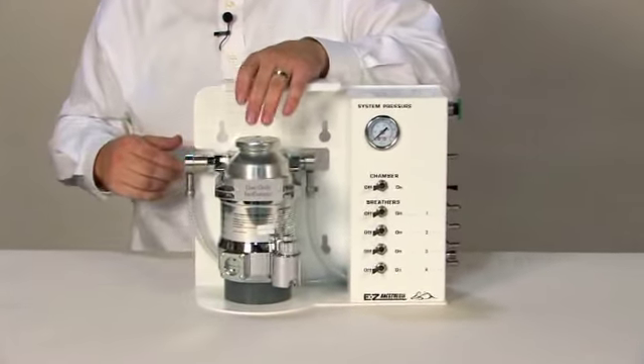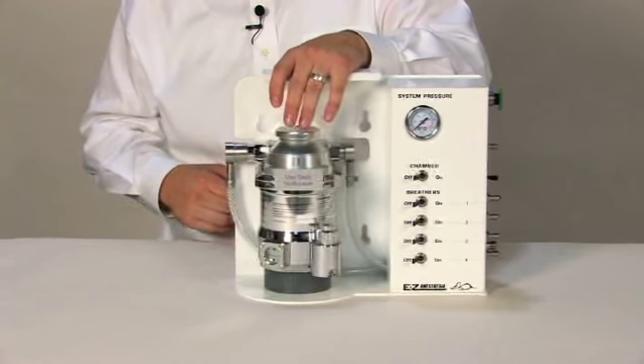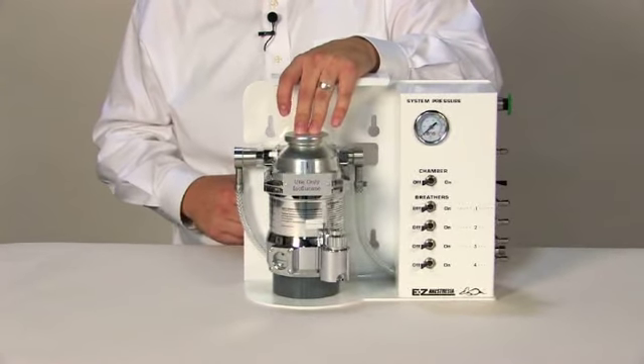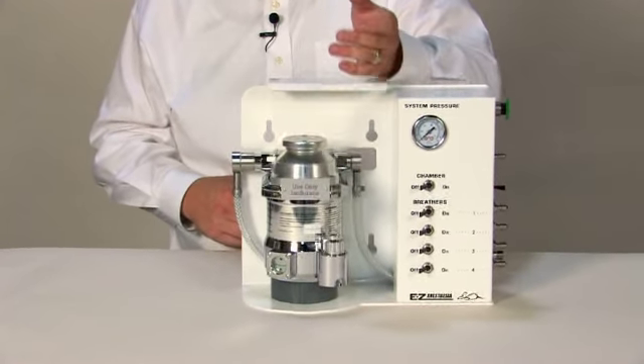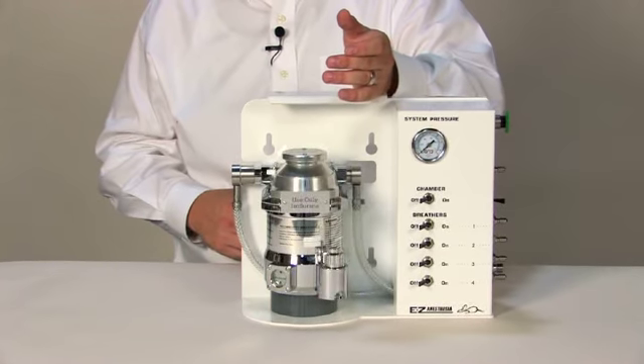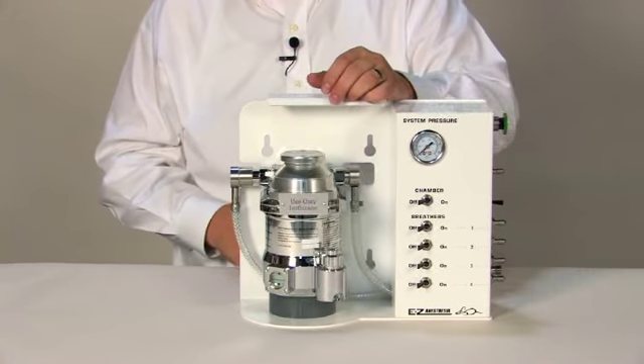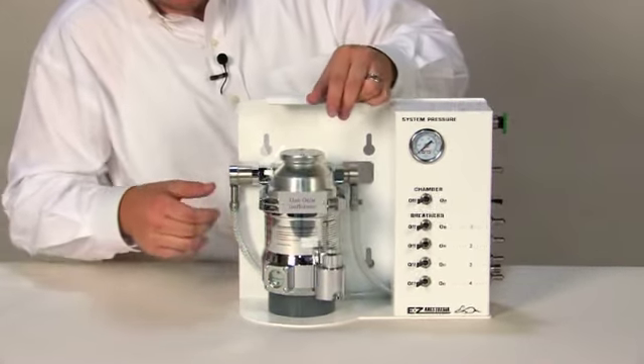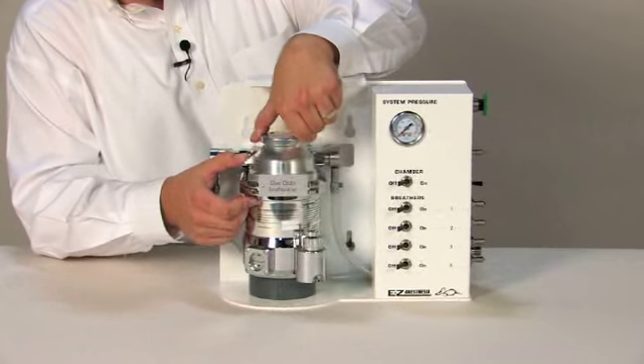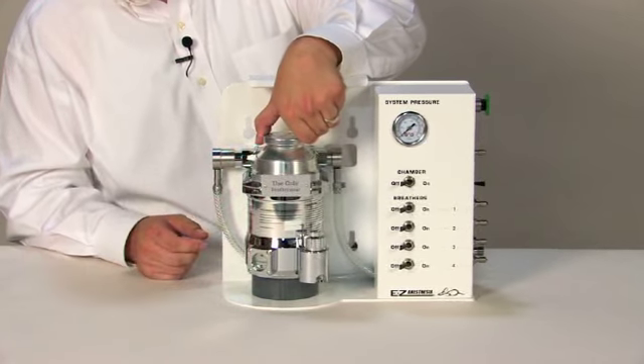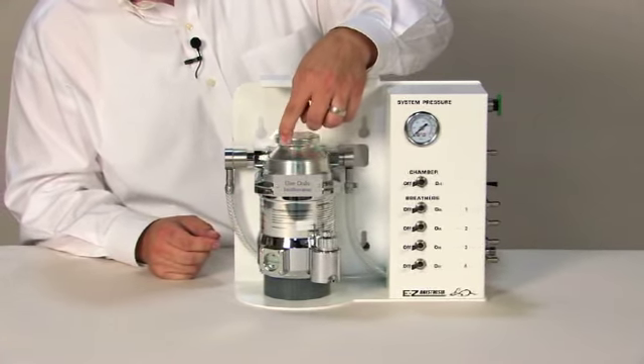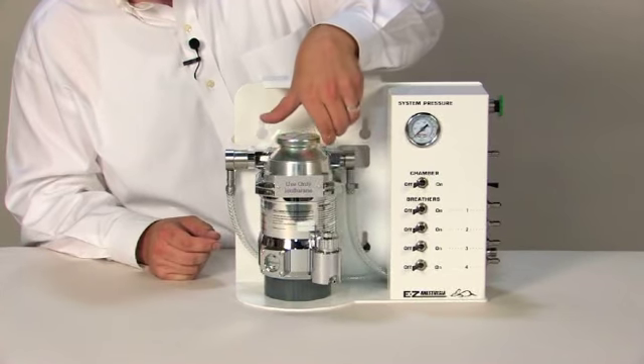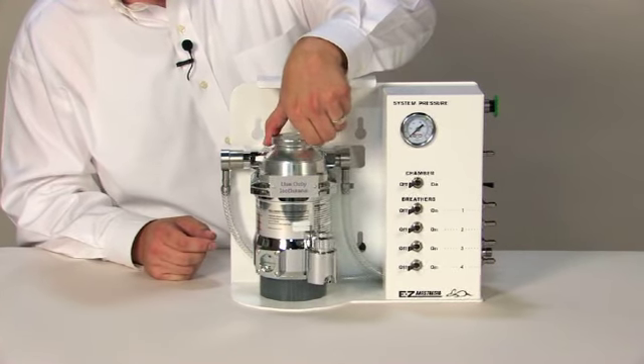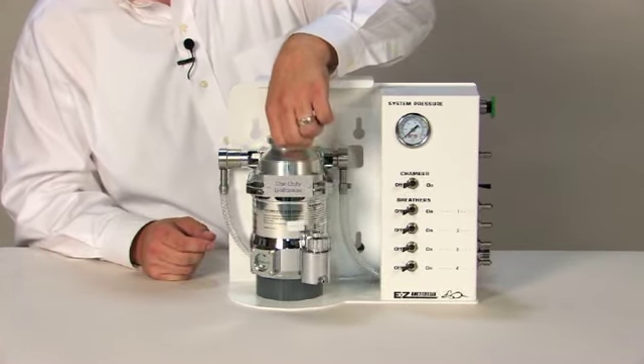This device is the vaporizer. The vaporizer blends the incoming oxygen with liquid isoflurane, generating an anesthetic vapor which is then delivered to the various components of the system. Isoflurane concentration is controlled using this dial on the top of the vaporizer. These numbers represent percentage, and the vaporizer outputs from 0 to 5% isoflurane concentration.